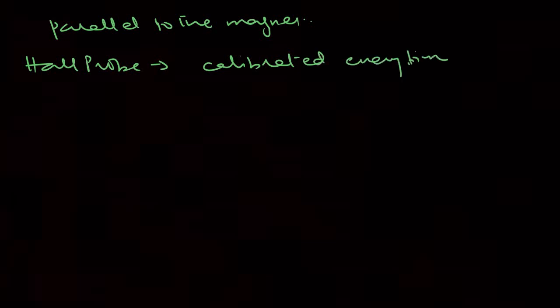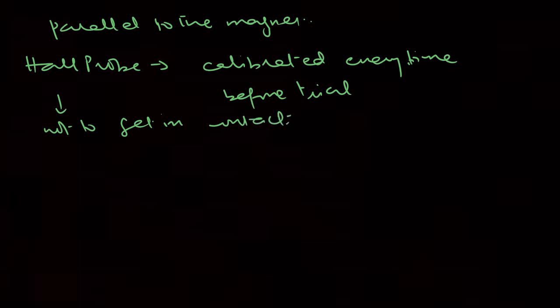So remember that the Hall probe is sensitive to heat. Do not allow the Hall probe to get in contact with oil, hot or cold. The Hall probe needs to be calibrated every time before the trial. Right? So for the Hall probe: calibrated every time before the trial, and not to get in contact with oil, either hot or cold. So just keep these details in place.